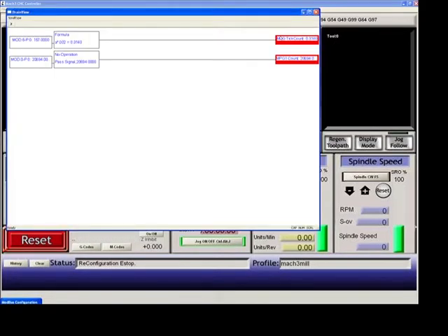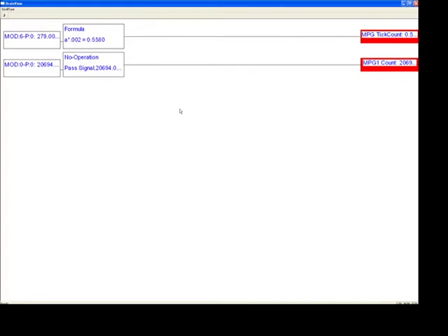So we'll go to brain control. You can see I have a Mod.io MPG1 brain here that is enabled and running. I'm going to hit View Brain so that you can see it run. Interesting here is we can see that I'm using Modbus address number 6, plug-in enabled, configuration 0, and we see a flashing number. This is the timer tick variable coming back from a Mod.io. The Mod.io is kind enough to send a message saying how long each message is taking. And it tends to be in 2 millisecond increments.